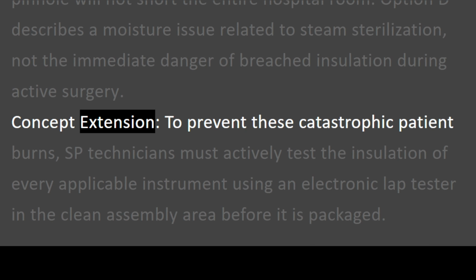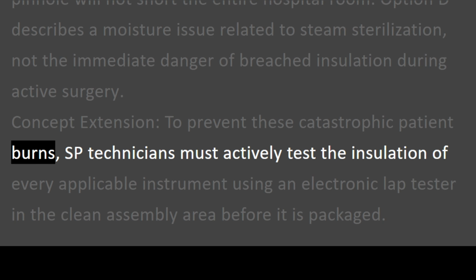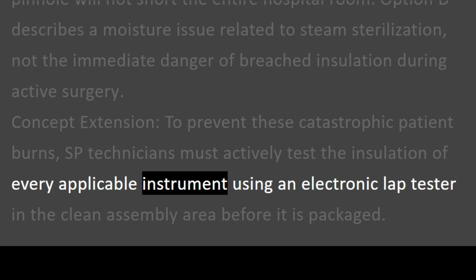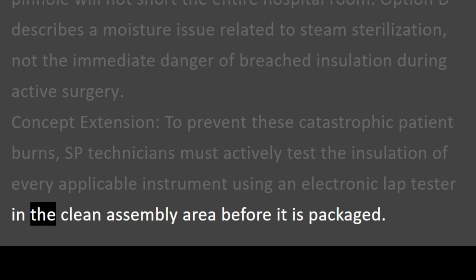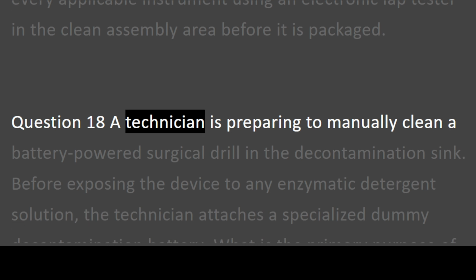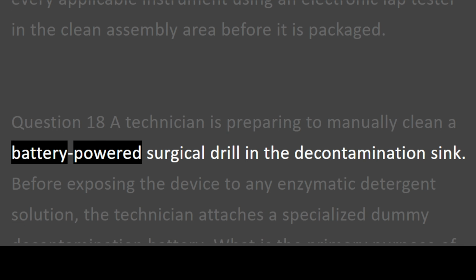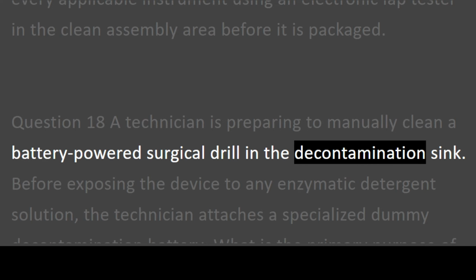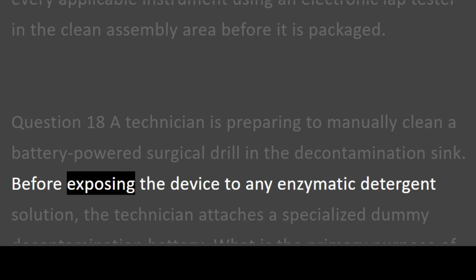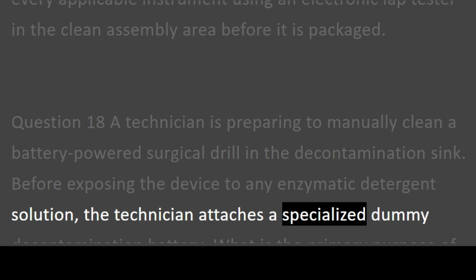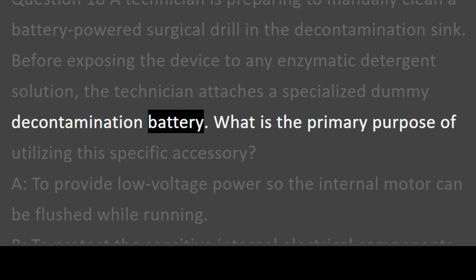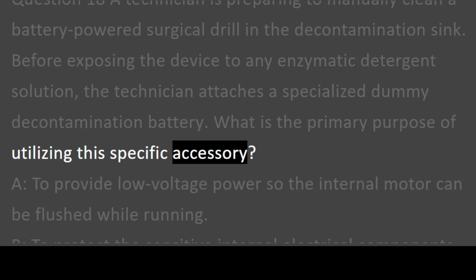Concept extension. To prevent these catastrophic patient burns, SP technicians must actively test the insulation of every applicable instrument using an electronic lap tester in the clean assembly area before it is packaged. Question 18. A technician is preparing to manually clean a battery-powered surgical drill in the decontamination sink. Before exposing the device to any enzymatic detergent solution, the technician attaches a specialized dummy decontamination battery. What is the primary purpose of utilizing this specific accessory?